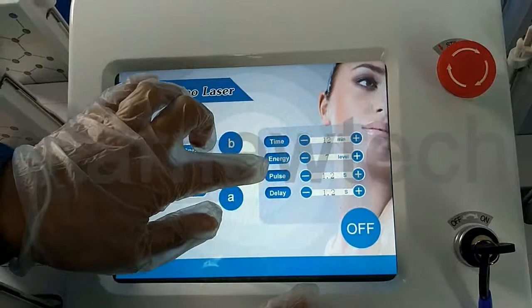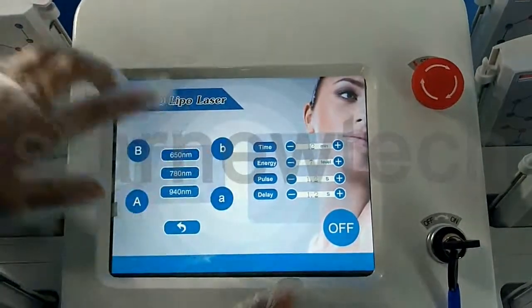For this: time, energy, pulse, and delay. Time is the treatment time — it's from 1 minute to 60 minutes. Energy is from 1 to 15 level. Pulse is from 0.1 to 5 seconds. Delay is from 0 to 5 seconds. Pulse means the work time on our skin. Delay is the stop time.